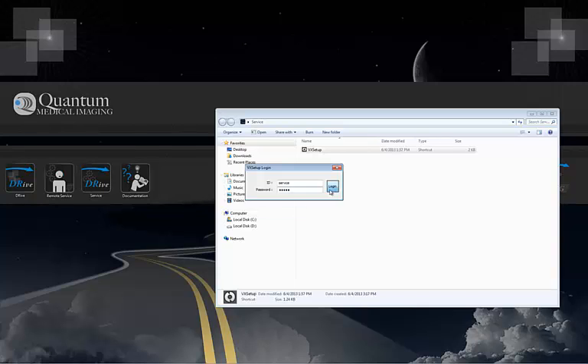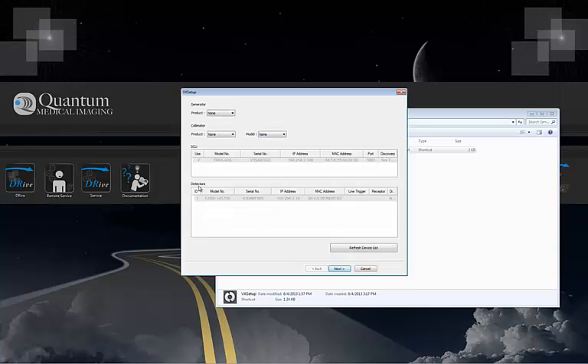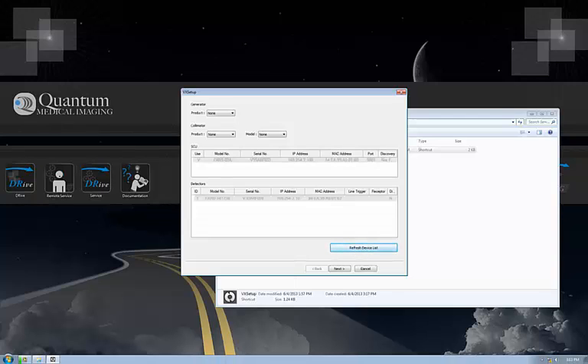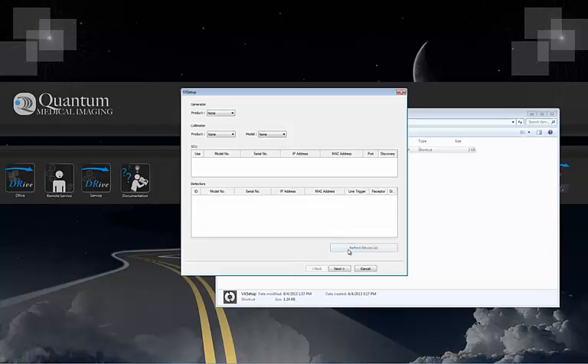Note in this example, the system control unit, the SCU, is off and the detector tethered cable is disconnected, so we don't see communication with either. Once I power on the SCU and press the refresh, communication is established with the SCU. But not until attaching the tethered cable to the detector do we see full connection established for both.